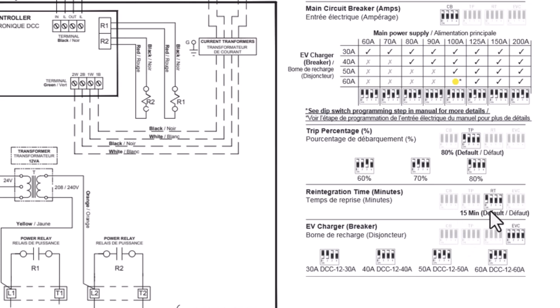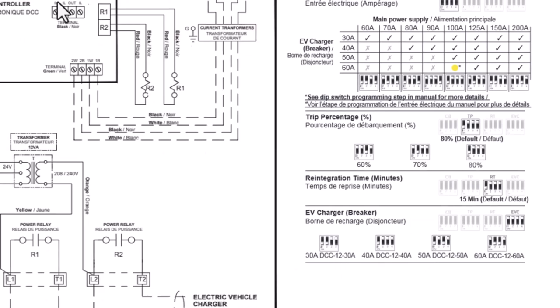And also there's a 15-minute delay. So if it senses the current is below that threshold that is set here under the trip percentage for a given amount of time, then it'll switch the power back to the EV charger. And that default is the 15 minutes here. And the EV charger breaker has to be set at an amperage that is 50% of your main power. So if let's say your main power is 100 amps, you have to set the dip switches so that it's half of that, so 50. So it would have to be in this sort of configuration here. So if we were at, let's say, 80 amp main power supply, then you would have to adjust the dip switches to be in this pattern right here for a 40 amp. And when I was installing my DCC-12, this is the one I have, when I didn't do it at 50%, the system didn't work. So I think that you have to set at 50% for the system to actually work.